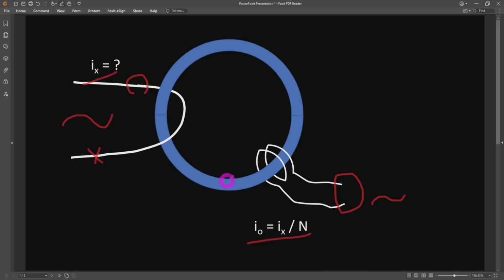But this right away runs into several problems. First of all, if I want to measure this current at a very, very high frequency, I'm going to have to shrink the size of this transformer significantly in order to be able to support the kind of magnetic flux variation it's supposed to have. And as the frequency gets lower and lower, I'm going to reach a point where I'm going to saturate this. Or if I put too much current through it, I'm going to saturate this core, in which case then I'll get a nonlinear effect, and then you won't be able to measure the current anyway.